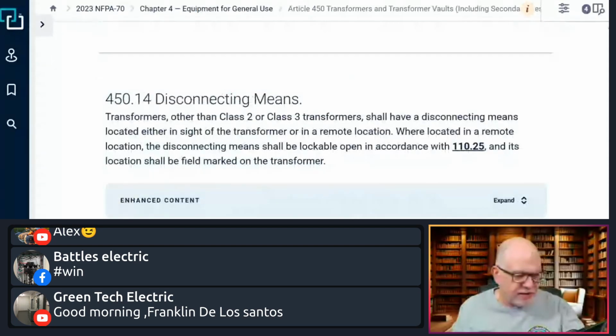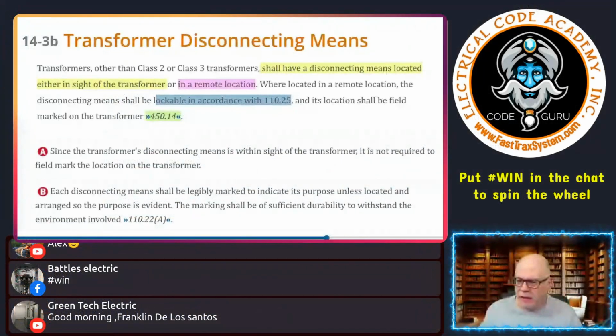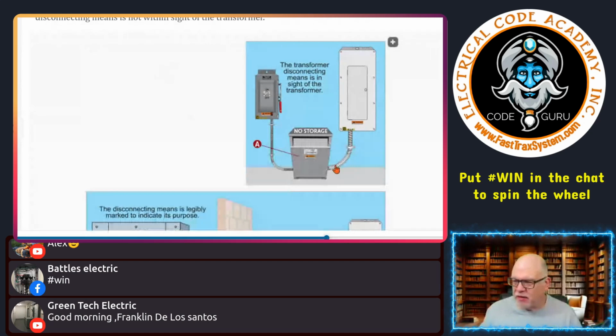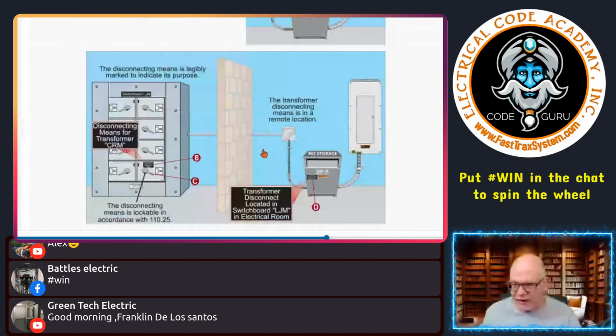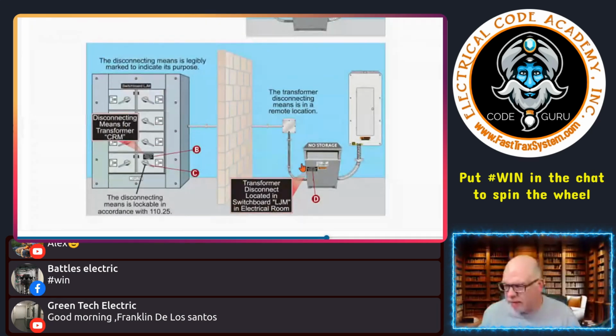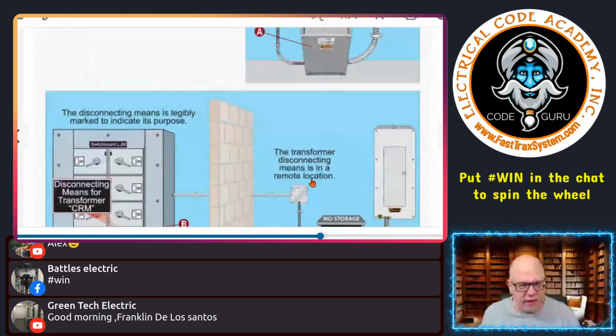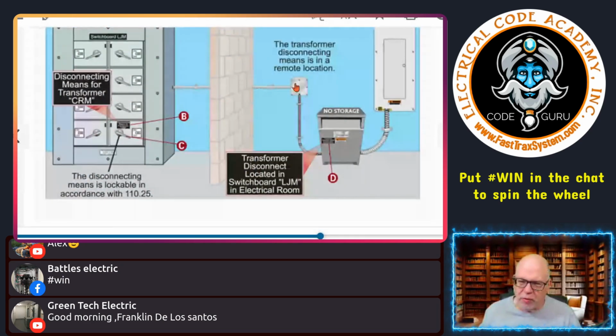So let's go down and look at the lesson, and this is what we're talking about right here. This is the graphic we're talking about, and I can blow this up a little bit for you. There we go, just enough. So here's an example where you've got your disconnecting means for the transformer, and here this means is lockable. It's got some kind of mechanism on here that once you're in the open position, you can put a lock on it, so nobody can inadvertently come and switch that on. It's the last thing you want.